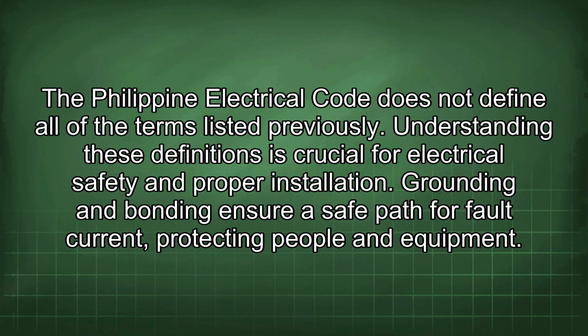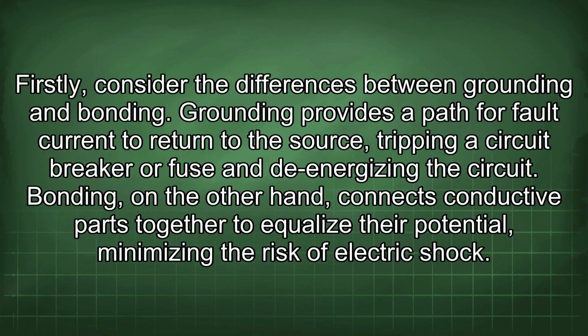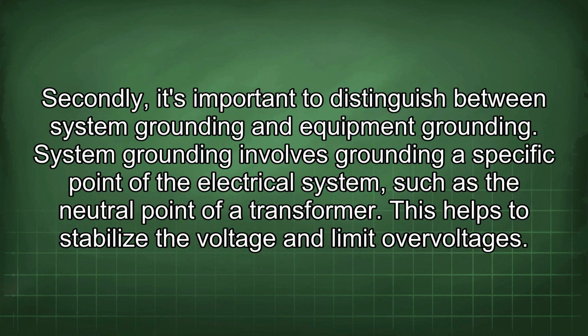Understanding these definitions is crucial for electrical safety and proper installation. Grounding and bonding ensure a safe path for fault current, protecting people and equipment. Firstly, consider the differences between grounding and bonding. Grounding provides a path for fault current to return to the source, tripping a circuit breaker or fuse and de-energizing the circuit. Bonding, on the other hand, connects conductive parts together to equalize their potential, minimizing the risk of electric shock.